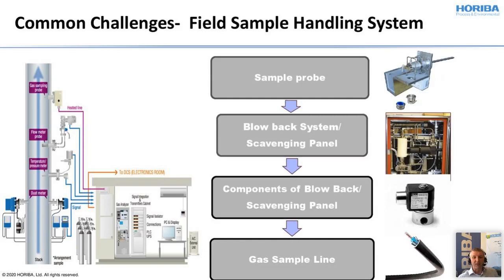Next topic is the blowback system at the sampling point. The blowback bundle or the scavenging bundle should be a heated one to avoid any condensation or choking of the sample line. It is found in some installations that the customer side sometimes has the instrument line and sample line bypassed and/or directly connected to the sample probe, which should be completely avoided. You will see some pictures later where you will see wrong or bad engineering and location.